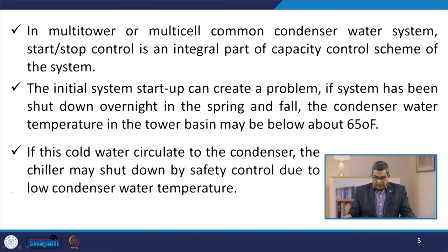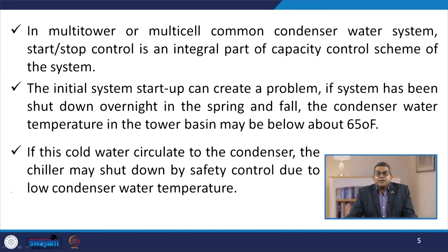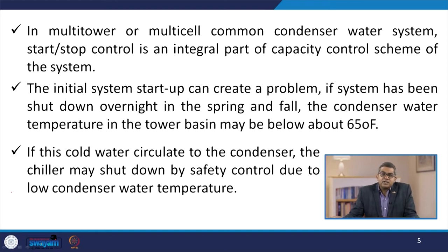In multi-tower or multi-cell common condenser water systems, start-stop control is an integral part of the capacity control system. Regarding initial system startup, this can create a problem if the system has been shut down overnight in spring and fall, and the condenser water temperature in the tower basin may be below 65 degrees Fahrenheit. If this cold water circulates to the condenser, the chiller may shut down by safety control due to low condenser water temperature.